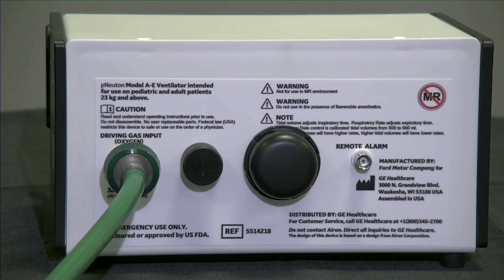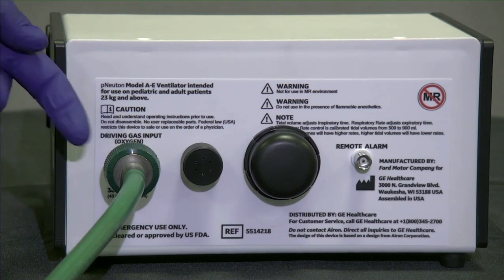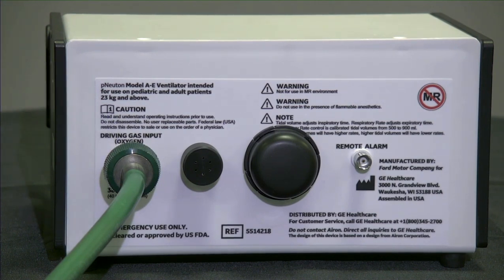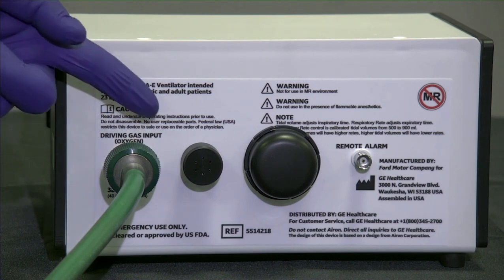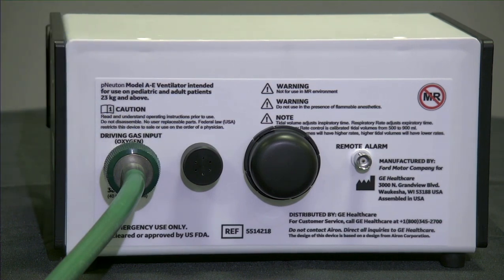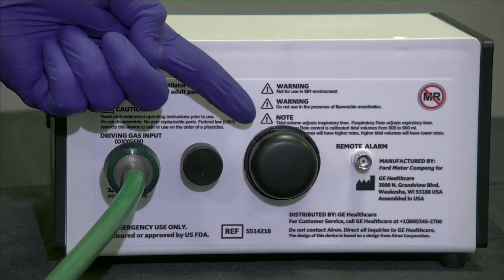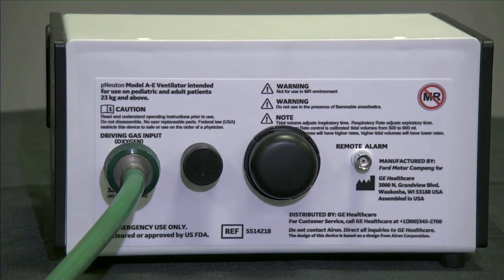Let's start with the features and controls of the rear panel. Gas input connection. The gas input connection requires connection to a high-flow oxygen source of 55 psi. Audible alarm. The audible alarm alerts when a patient disconnect has occurred or when the oxygen gas pressure drops below 30 psi. Ambient air intake. The ambient air intake filters air as it enters the ventilator's entrainment system.